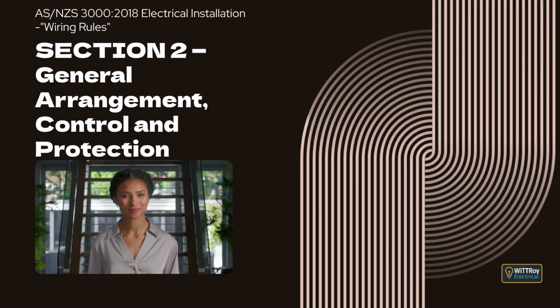If the voltage disappears and then suddenly returns, some equipment can start unexpectedly. Imagine a guillotine, a press, or a powered gate suddenly coming back to life. If the voltage drops too low, motors may struggle to start or run, which can cause overheating or even failure. So we provide undervoltage protection when low voltage could create danger for people or property. But if the equipment can safely handle a short interruption without danger, then undervoltage protection is not required.